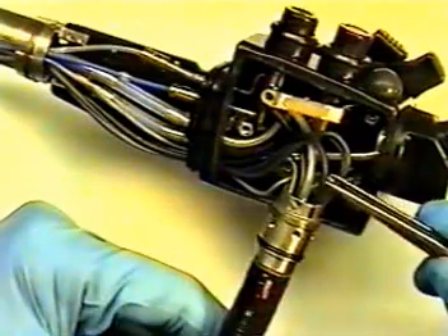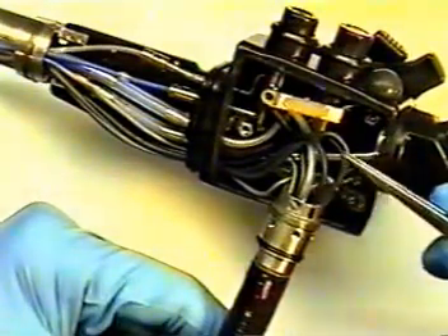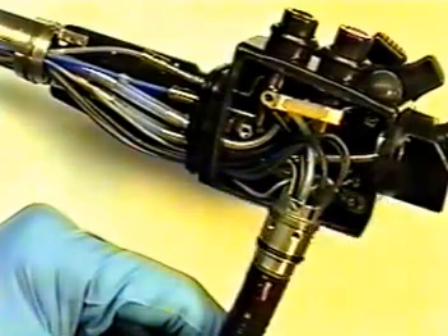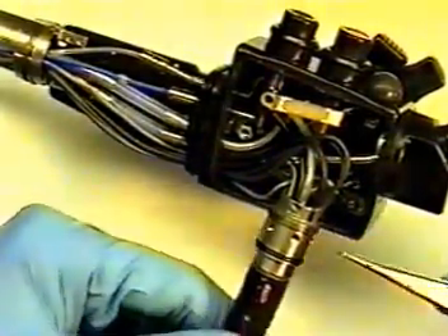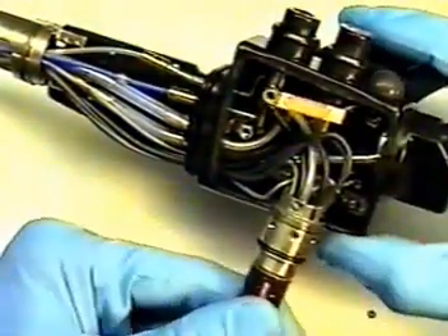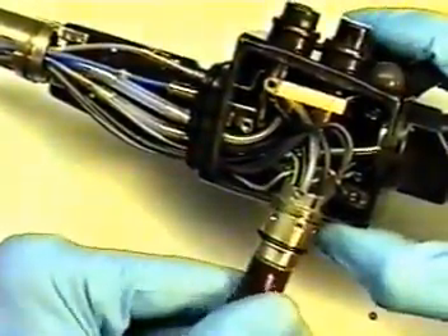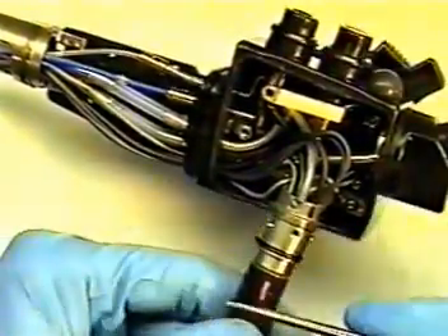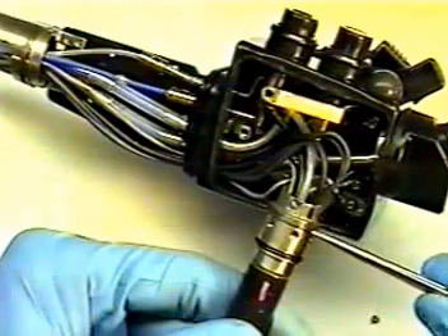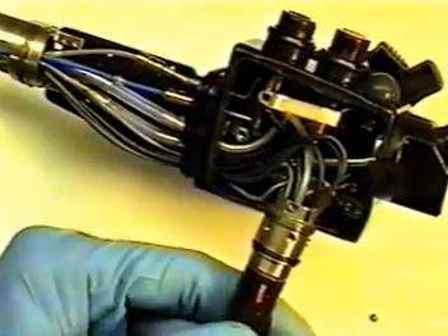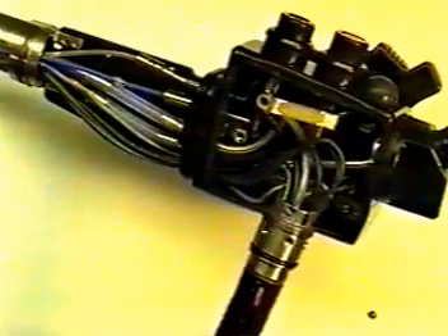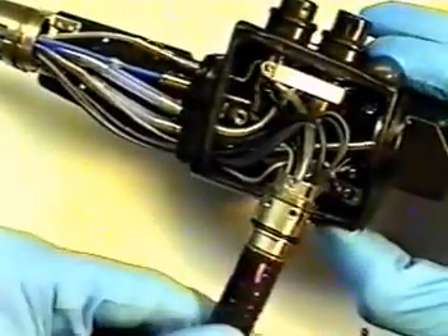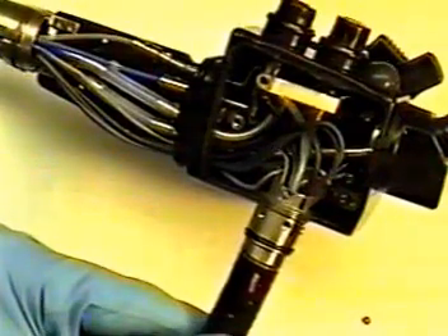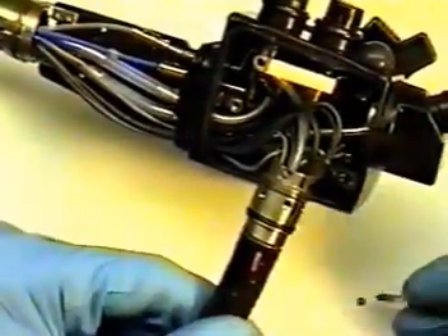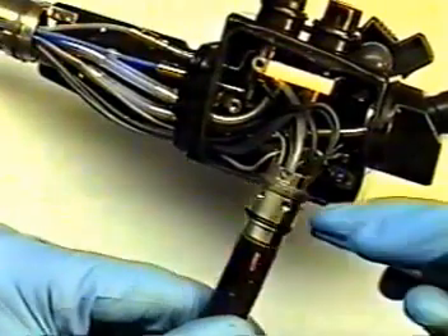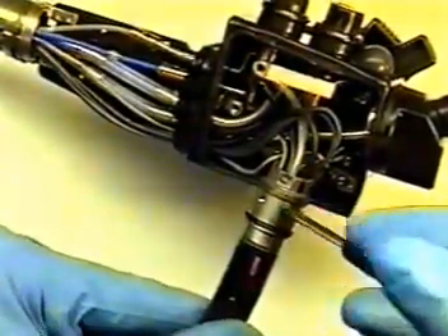Once the illumination bundle and CCD wire harness has been passed through, leaving a small amount of slack inside the body, locate your countersunk stainless steel screws. You'll need to orientate the light guide umbilical section to the scope by usually a factory marking or mark that you had previously made. Line up the umbilical control section back to the mark. Using your Phillips screwdriver, replace each countersunk stainless steel screw.